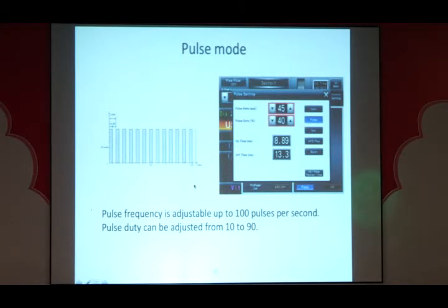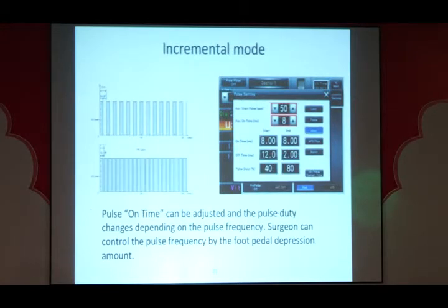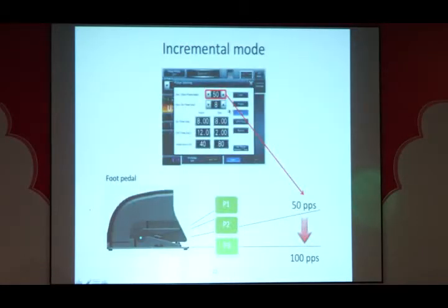which gives us the least possible energy consumption. The incremental mode has an advantage in the sense that it fixes the on time, but the frequency can be changed by your foot pedal. So when you start, if you have 50 pulses in the beginning and you are pressing on your foot pedal, it gradually becomes 100, and your on time remaining the same, your duty cycle then changes from 40% to 80% as you move your pedal down, which allows you to do the phaco-emulsification much more efficiently. When you want more energy, you get a greater duty cycle.